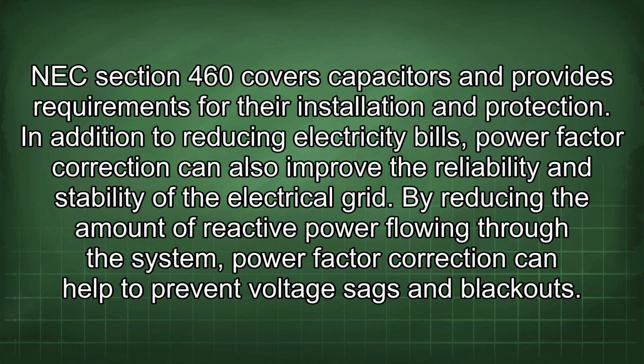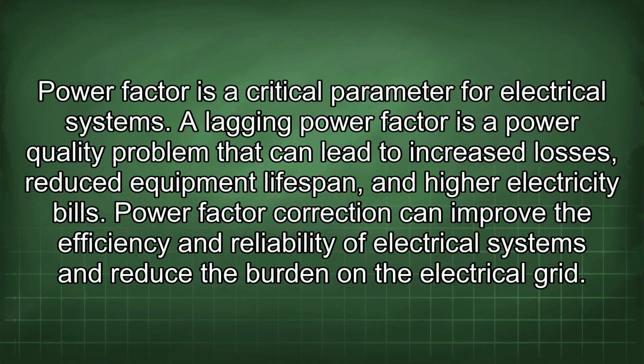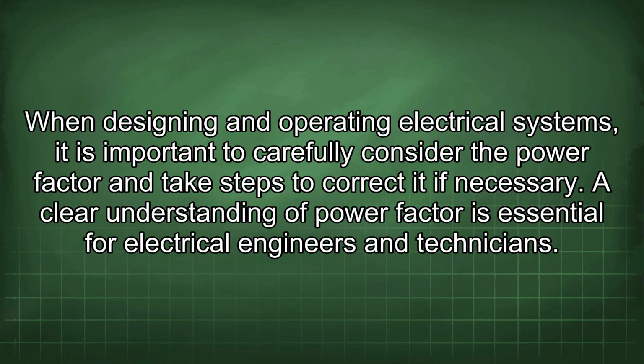In addition to reducing electricity bills, power factor correction can also improve the reliability and stability of the electrical grid. By reducing the amount of reactive power flowing through the system, power factor correction can help to prevent voltage sags and blackouts. Power factor is a critical parameter for electrical systems. A lagging power factor is a power quality problem that can lead to increased losses, reduced equipment lifespan, and higher electricity bills. Power factor correction can improve the efficiency and reliability of electrical systems and reduce the burden on the electrical grid. When designing and operating electrical systems, it is important to carefully consider the power factor and take steps to correct it if necessary.